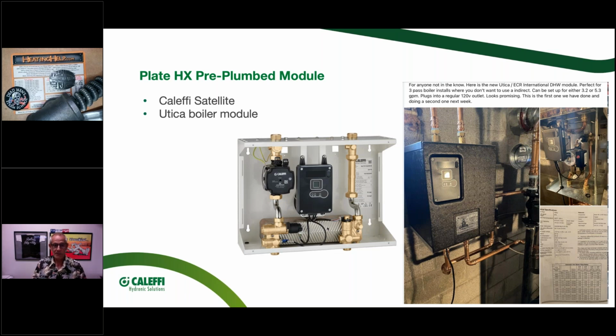So sometimes you can be fooled into thinking it's always the hard water causing the problem, and that's true for any type of heat exchange, whether it's a combi boiler, a shell and tube, an indirect tank, or a reverse indirect tank. It's all sensitive to scaling on the metal surface areas.